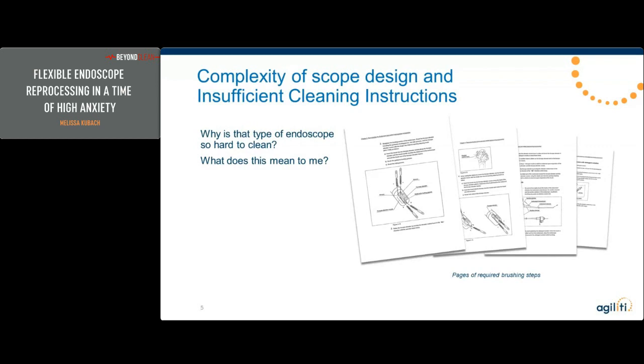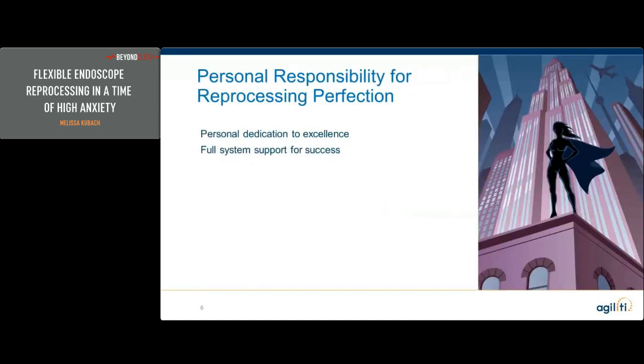So what does this mean to you if you do not reprocess this type of scope? It means the bar has been raised for reprocessing flexible endoscopes, regardless of type, model, or manufacturer. Your process and associated documentation are likely to draw greater scrutiny from external surveyors and from internal infection preventionists. You are now expected to be perfect, even when flexible endoscopes are a small portion of what you do during your shift.